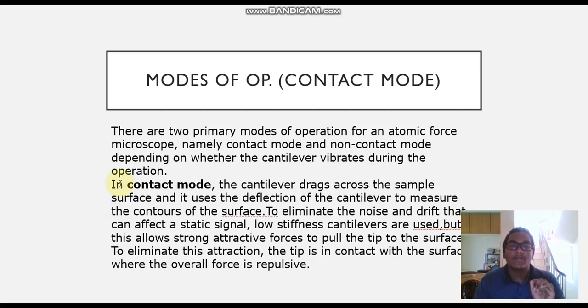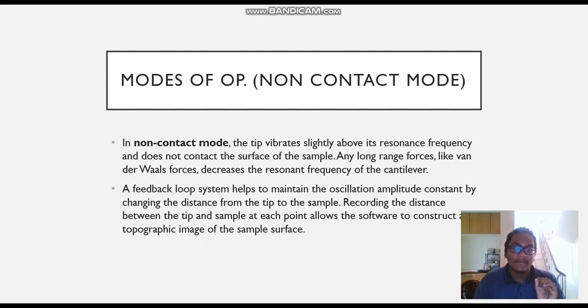When we talk about the modes of operation, there are two modes basically, contact mode and non-contact mode. In contact mode, the cantilever drags across the sample and it uses the deflection of the cantilever to measure the contours of the surface. When you talk about the non-contact mode, the tip vibrates slightly above the resonance frequency and does not contact the surface of the sample. But one must consider that forces such as van der Waals forces decrease the resonant frequency of the cantilever. So we must keep that in mind and look into it with the help of a feedback loop system which helps to maintain the oscillation amplitude constant by changing the distance from the tip to the sample.